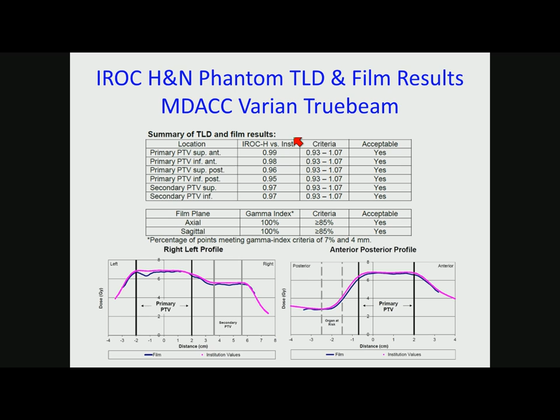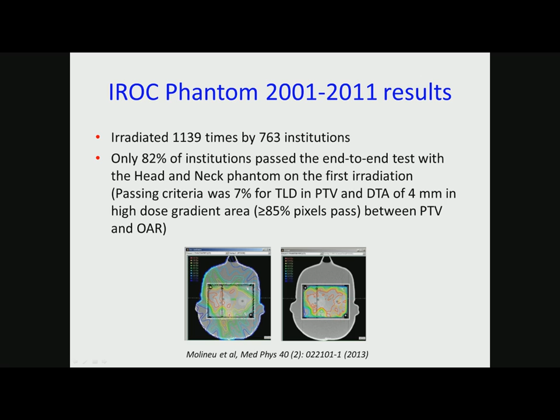Initially, this was only for the NCI patients, putting patients in protocols, but now anyone can ask for this Phantom and get it. It's been irradiated 1139 times by 763 institutions. Only the head and neck Phantom. They also have other Phantoms available. Only 82% of institutions pass the end-to-end test with the head and neck Phantom on the first irradiation, which was not very nice, with such a loose tolerance of 7% for the TLD and distance to agreement of 4 millimeters.